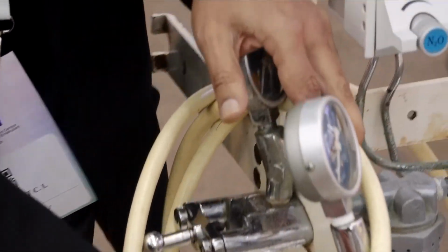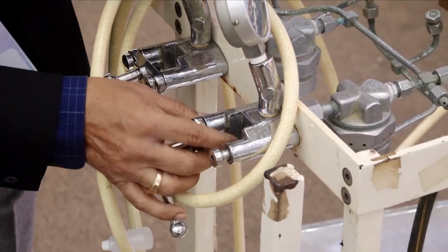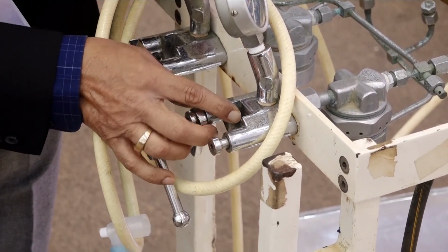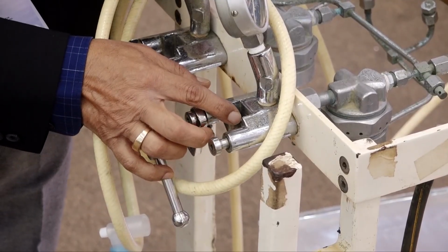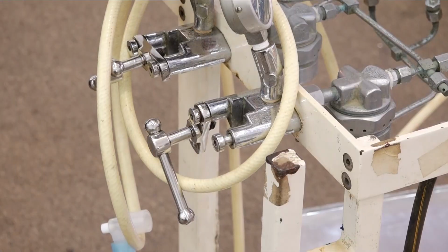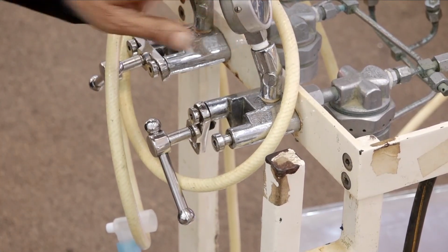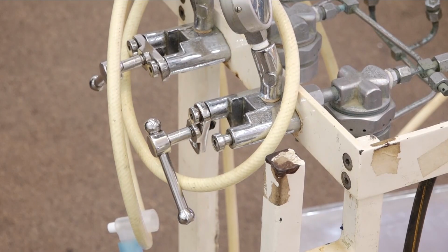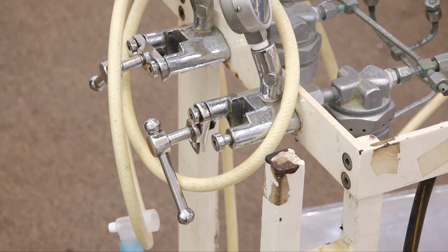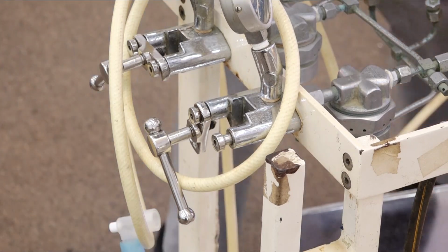You can just see the pins for the pin index. And above the pin index pins, you have the nipple where the port of the cylinder is fixed, where the gases will flow inside. When you fix the cylinder onto the yoke assembly, it is very important that you always look for what is called a Bodok seal, because it will make sure that there is no leak between the cylinder and the yoke assembly or the machine.